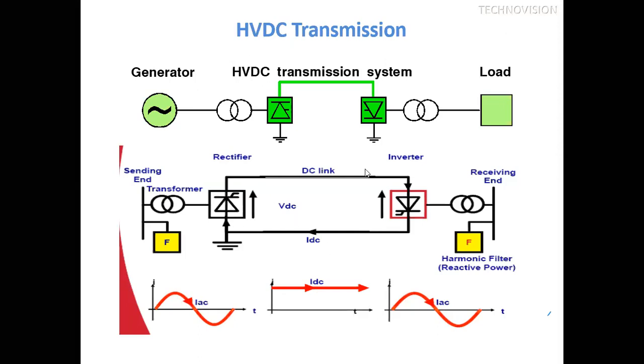Okay, and again here DC is converted into AC, and the return current always goes either through the metallic return when a healthy pole is available. Otherwise, it will go through the ground. So this is, we can say, monopolar. It's a ground return mode.